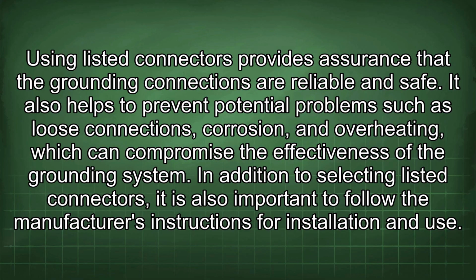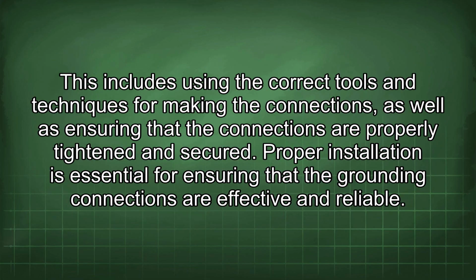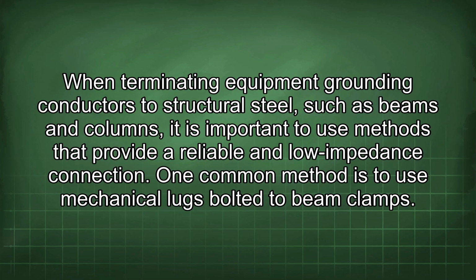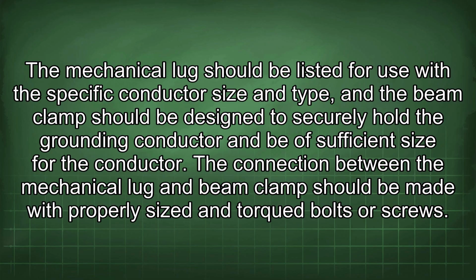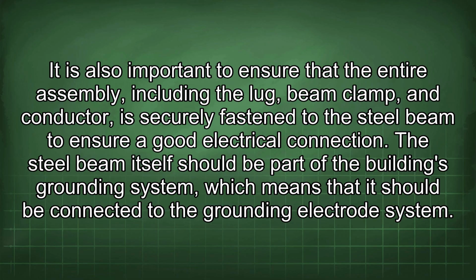In addition to selecting listed connectors, it is also important to follow the manufacturer's instructions for installation and use. This includes using the correct tools and techniques for making the connections, as well as ensuring that the connections are properly tightened and secured. Proper installation is essential for ensuring that the grounding connections are effective and reliable. When terminating equipment grounding conductors to structural steel, such as beams and columns, it is important to use methods that provide a reliable and low-impedance connection. One common method is to use mechanical lugs bolted to beam clamps. The mechanical lug should be listed for use with a specific conductor size and type, and the beam clamp should be designed to securely hold the grounding conductor and be of sufficient size for the conductor. The connection between the mechanical lug and beam clamp should be made with properly sized and torqued bolts or screws. It is also important to ensure that the entire assembly, including the lug, beam clamp, and conductor, is securely fastened to the steel beam to ensure a good electrical connection.